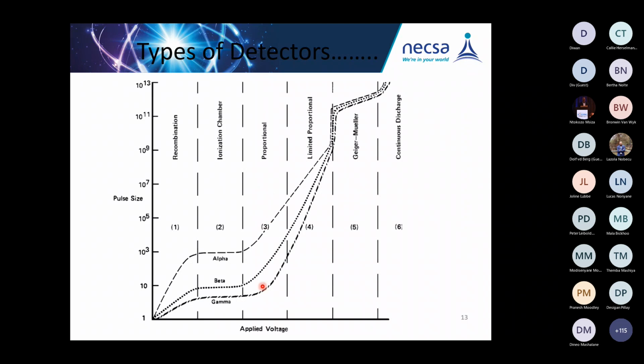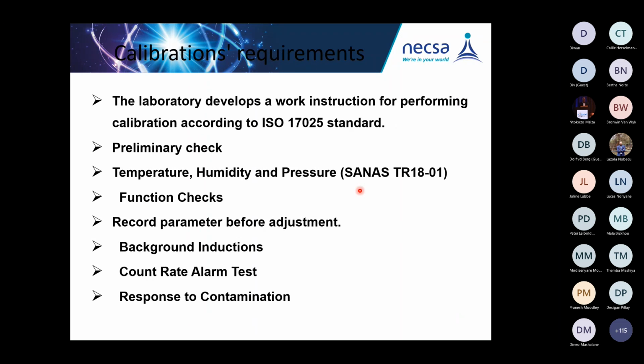This is the part where you have your gas proportional counter, the detector that I was showing you. It operates at these high voltage levels. As you can see, you start from 1 and then you increase the high voltage. And from this is the limited gas proportional counter detector. And this is your Geiger-Müller. The Geiger-Müller is the one we normally call the GM tube. That is the one that you use for radiation survey. Most of them have the GM tube. That is the Geiger-Müller tube. Calibration requirements. The laboratory develops the work instruction for performing calibration according to ISO 17025.